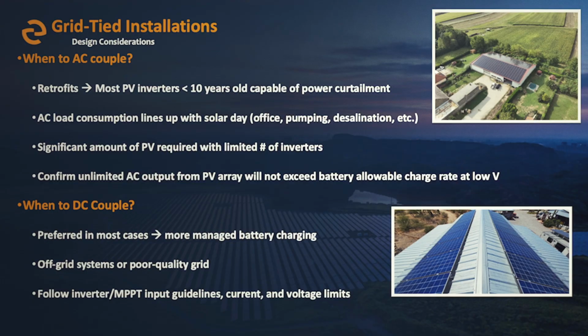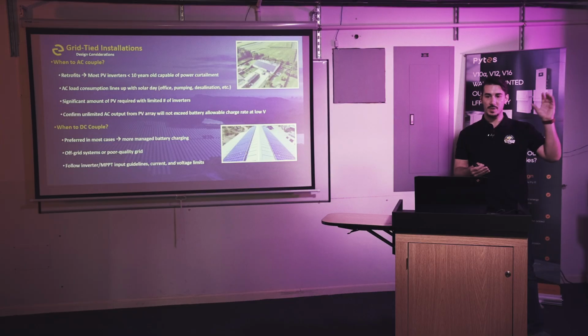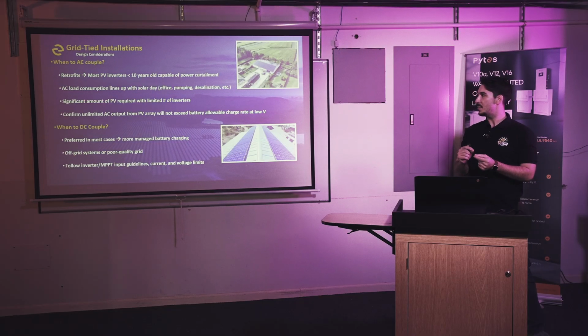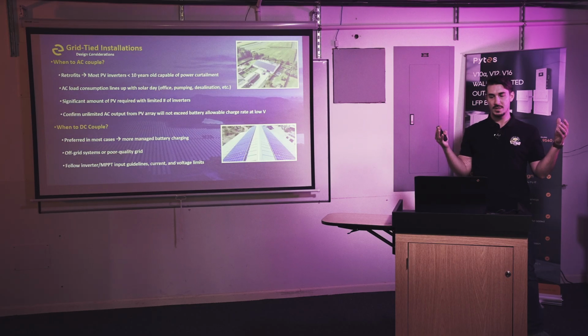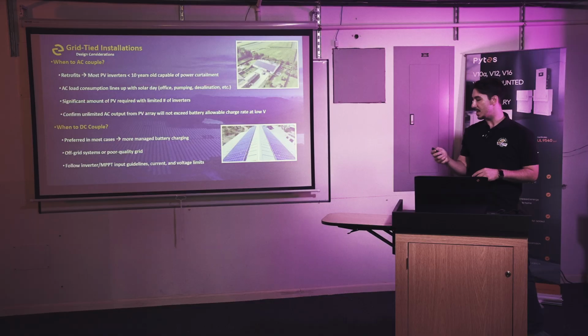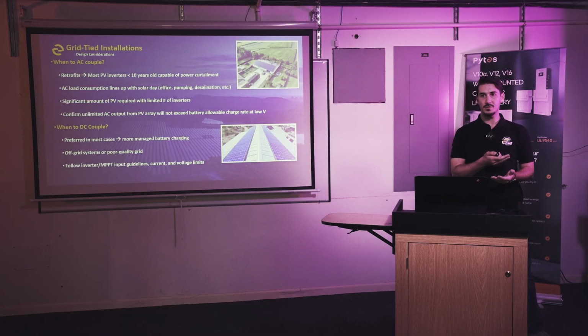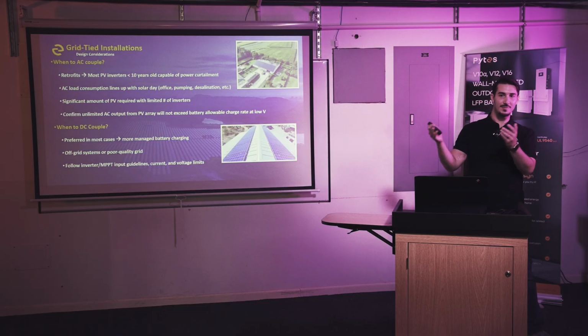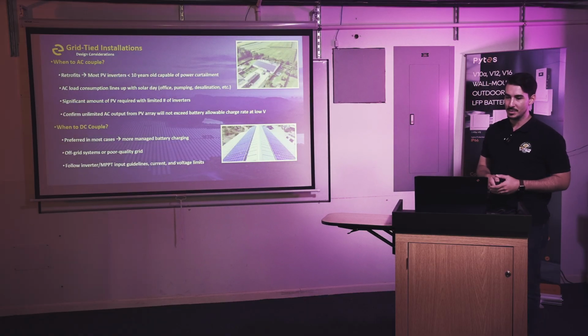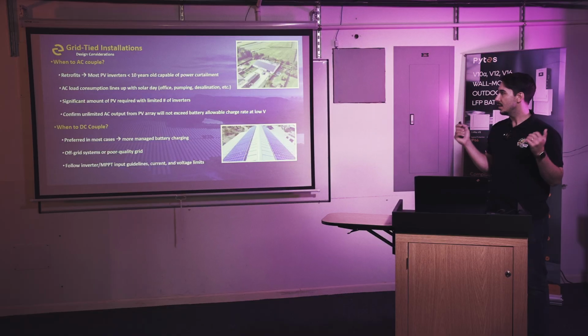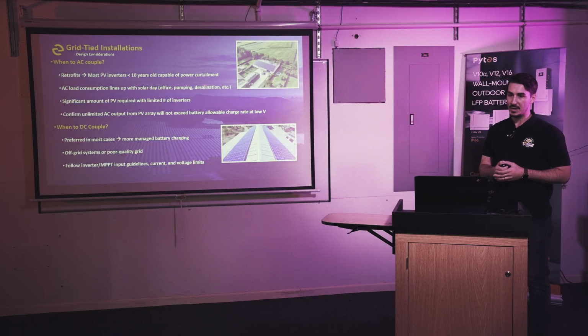What happens when we do AC coupling is the battery inverter, or I should say the solar converter, would frequency shift, and the PV inverter sees that and then knows to either slow down or speed up its charging. Well, sometimes that doesn't happen fast enough, and then you can have the situation where the total unlimited output of your PV array is dumped into the batteries. Maybe that's only happening for a brief moment, but again, because these batteries have a BMS, if you exceed what they're designed to accept, that BMS is going to trip and disconnect from the battery inverter. Now the solar doesn't have a frequency to show to the PV inverter, so it's going to basically cause the whole system to crash. And again, if you're doing AC coupling, make sure you've got enough batteries. That would be my main advice.